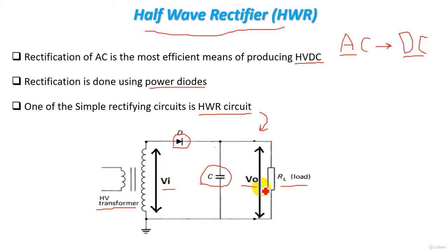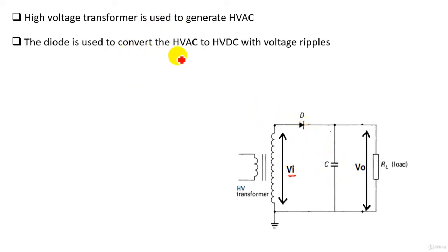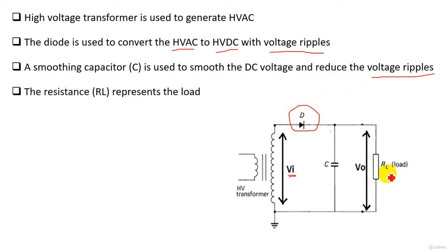Let's see the function of each component. The high voltage transformer steps up the voltage to obtain high voltage AC, which is the input to our rectification circuit. The diode converts high voltage AC into high voltage DC with voltage ripples. The capacitor is used to smooth the DC voltage and reduce the voltage ripples. The resistance R_L represents our load or insulator.